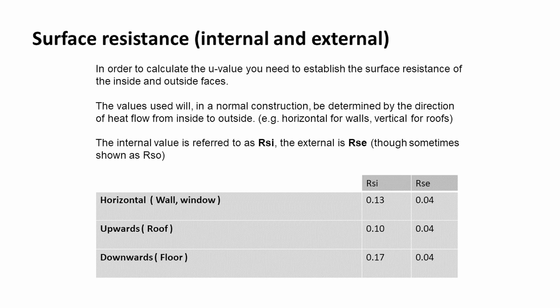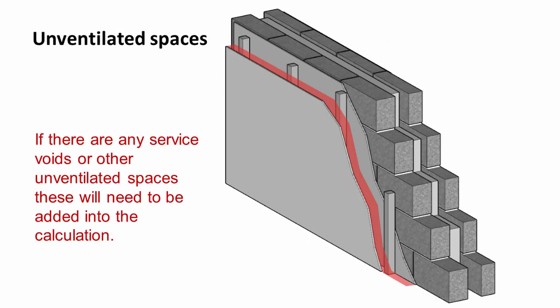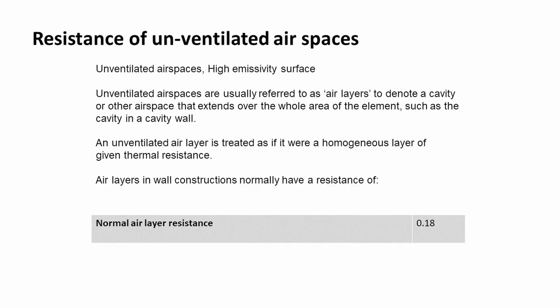We also have values for the resistance of unventilated airspaces within the construction, usually referred to as air layers. These are cavities or other airspaces that extend over the whole area of an element — not just a small pocket of air. We would give an unventilated air layer treatment as if it were a homogeneous layer with a given thermal resistance of 0.18.